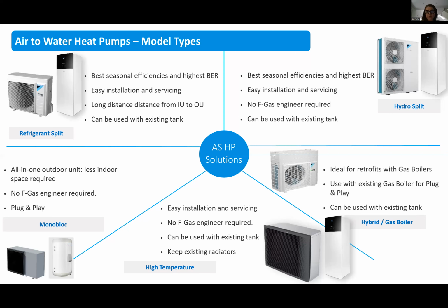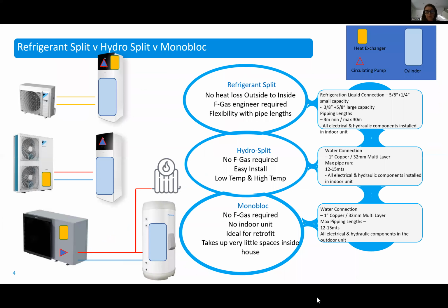So just to give you the difference between splits and monoblocks. Generally, refrigerant splits would be one of the most common types of air-to-water heat pumps available on the market. With the refrigerant split, you've got your refrigerant line going between your indoor and your outdoor unit. The big difference between splits, hydro splits and monoblocks is the location of the heat exchanger. The heat exchanger here is represented in the little yellow triangle, and it's a part of the refrigerant cycle. So wherever the refrigerant cycle is, the heat exchanger will be. With a refrigerant split, you have your refrigerant line going between the indoor and the outdoor, so it's located in the indoor unit. In the hydro split and the monoblock, the refrigerant cycle is contained within the outdoor unit, and so the heat exchanger is in the outdoor unit.